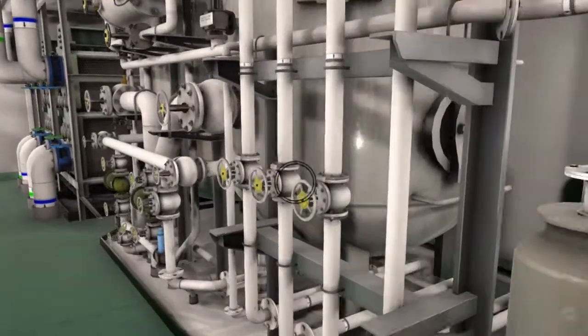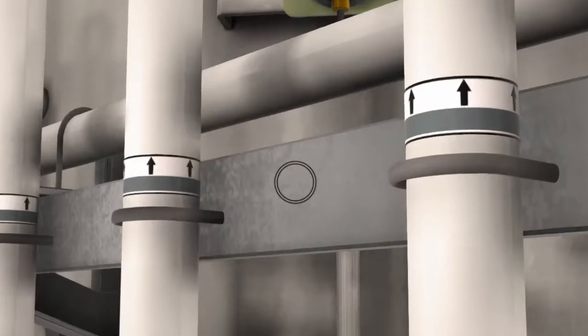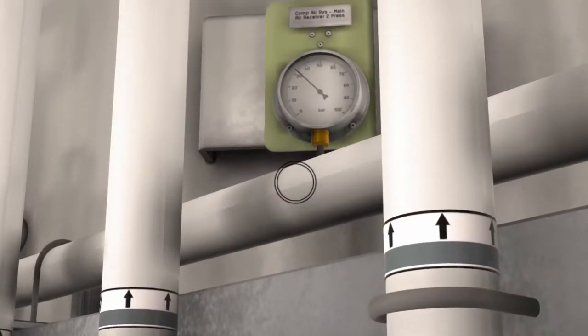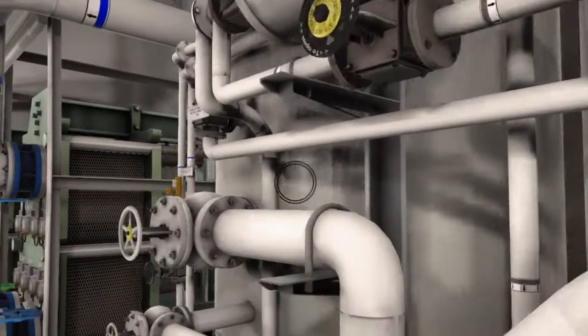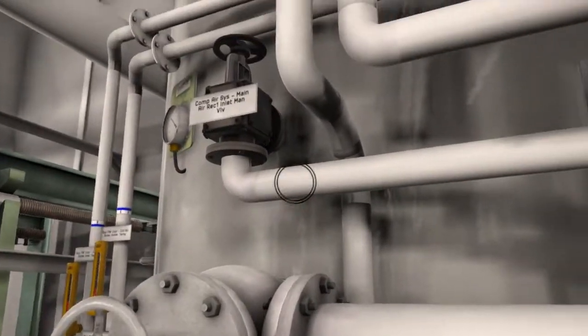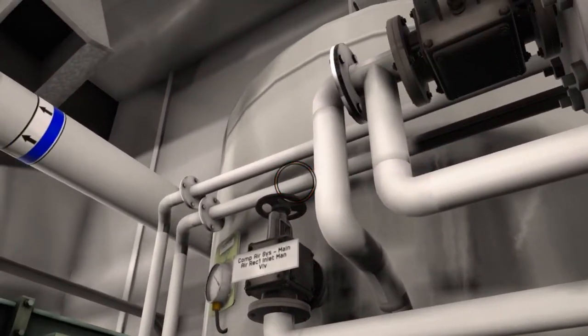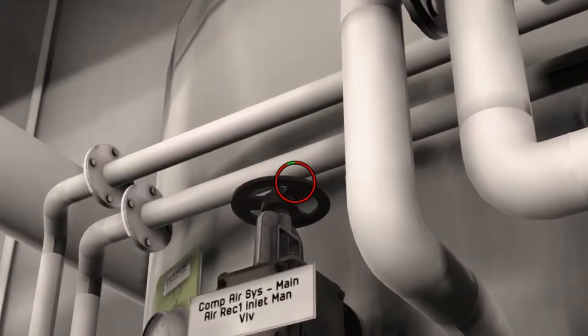When everything is set, we check again the pressures if it's fully filled up. The filling lines of the compressors are interconnected and can fill two air bottles simultaneously, even the three compressors can do so as long as the power requirements adhere to its capacity.